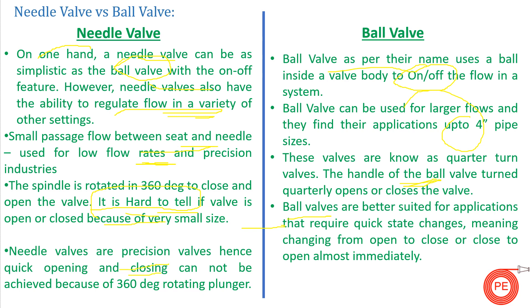Needle valves are precision valves, so quick opening and closing cannot be done because the handle must be rotated 360 degrees. Ball valves are used where quick opening or quick closing is required, since only a quarter turn of the handle is needed. Additionally, both needle valves and ball valves are used as root valves in instruments. However, in precision industries or complex systems where inaccurate instrument readings are unacceptable, needle valves are preferred. In normal or non-hazardous systems like water service, ball valves may serve as root valves.